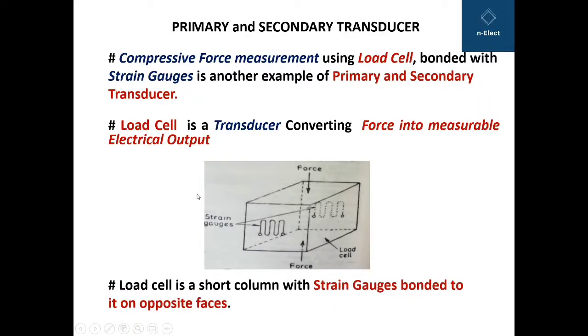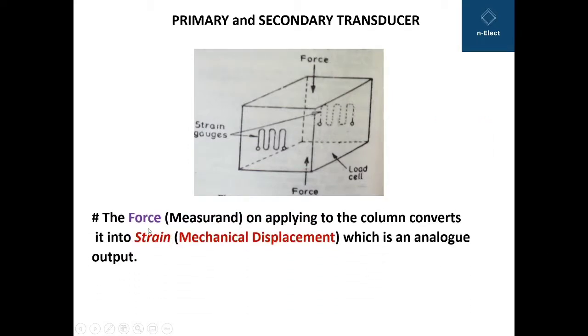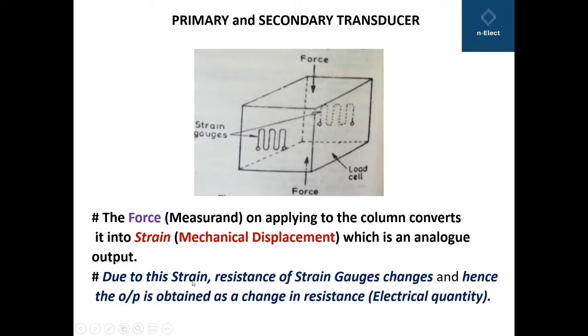We will see how it happens. The load cell is a short column with strain gauges bonded to it on opposite faces. The force applied to the column converts it into strain on the strain gauges. Strain is a mechanical displacement, which is an analog output. Due to this strain, the resistance of the strain gauges changes, and hence the output is obtained as a change in resistance, which is an electrical quantity.